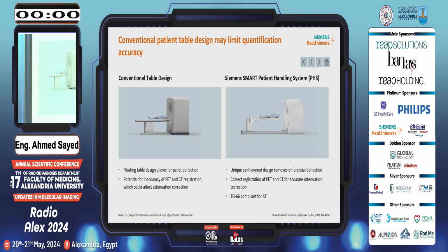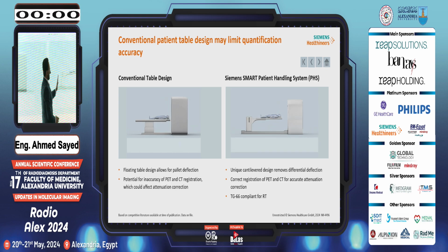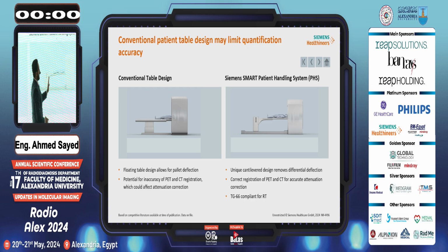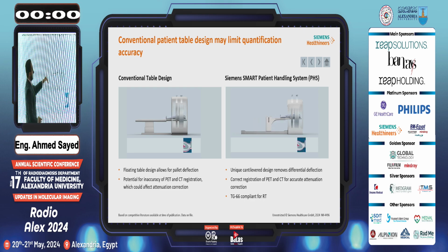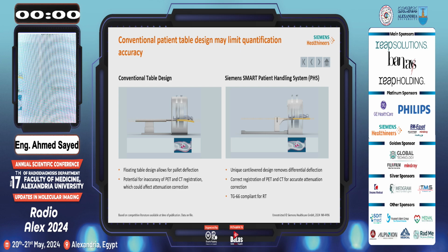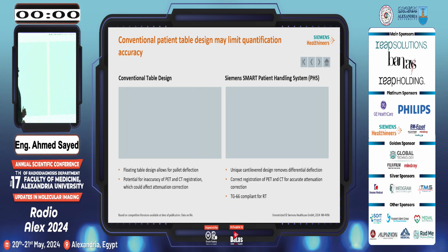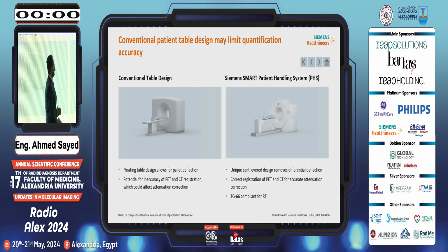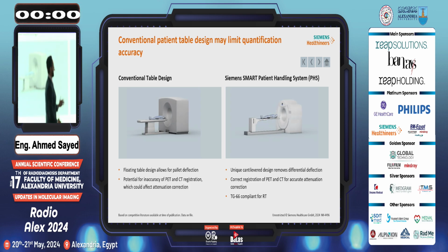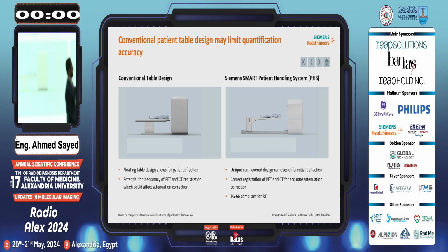Now we have to look at our design, the Siemens smart patient handling system. All the table moves itself with the patient, not only the tabletop. So there is no deflection. So no deflection in the Siemens design.